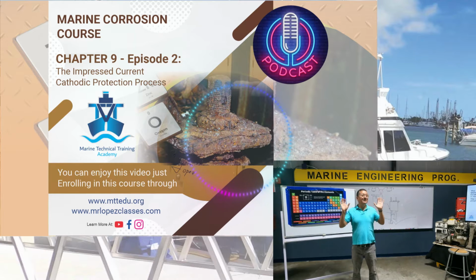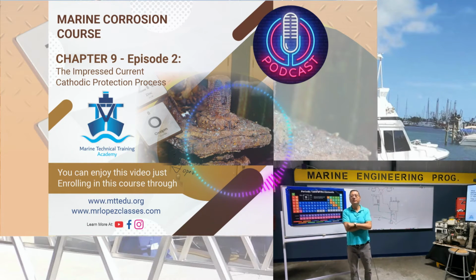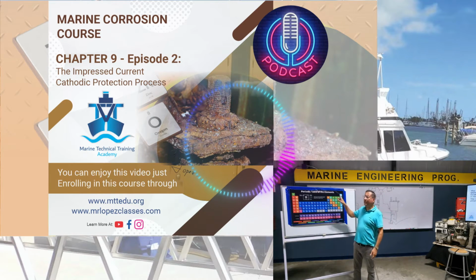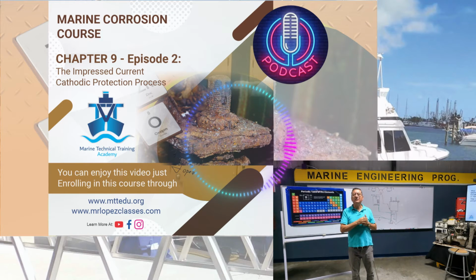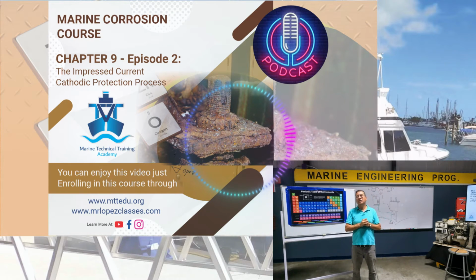You see, the pipe is protected with the anode. The anode is on the ground, inserted on the ground, separated from the pipes, and look, the negative is connected to the structure on top, and the anode creates the flow of electrons, and the electrons saturate the pipe, and the pipe is protected. The oxygen doesn't corrode the pipe. Wow! Yes, my friends, this is the procedure to protect the steel pipes in the oil companies.